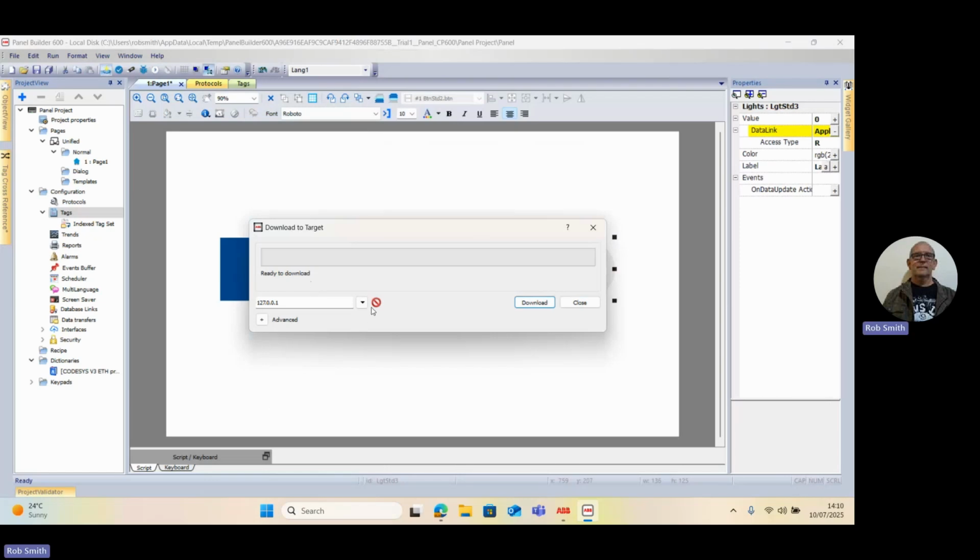So now it's finished. Now if I select this downward button, I should be able to see all the HMI screens that are connected to this network. So you can see I've got 8 of them. So again, I'll look to my cabinet. It says HMI is 192.168.1.026. So this is the one I want to send it to. And I'm going to press download. Now that is going to send that image to the screen.